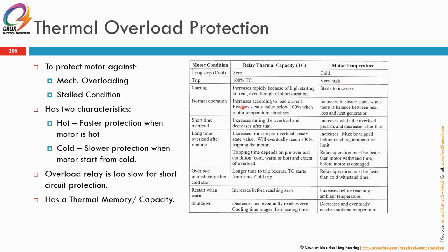In normal operation, the thermal capacity increases according to the load current and reaches a steady state value below 100% when the motor temperature stabilizes. So when you are running at full load current, the thermal capacity should never ever reach 100%. Either you have put the setting wrongly for the cooling and heating constants, or your motor is having a problem, like actual overloading.